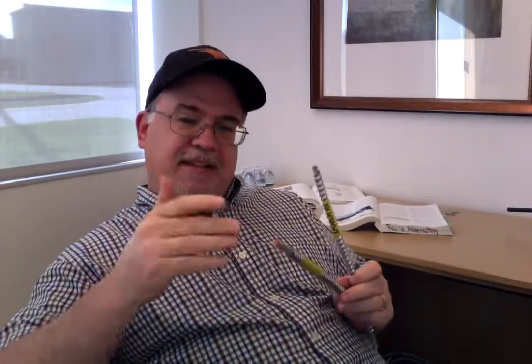Now, UL 1569 says that that equipment grounding conductor could be bare or it can be insulated. Most manufacturers will choose to insulate their equipment grounding conductor in a traditional MC cable. Just so you know that it's possible that you could have a bare in there. Now, with that said, let's suppose I have a typical MC cable that's got an insulated equipment grounding conductor and an additional isolated ground conductor in there.